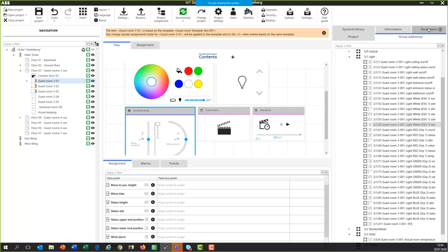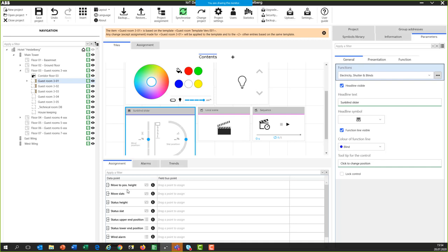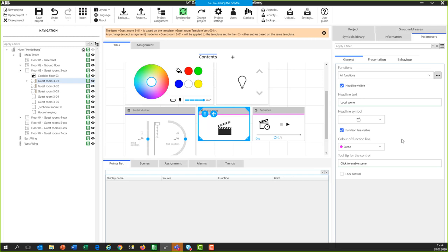For the sunblind shutter control, in the parameters you can adjust icons and text. The assignment objects include move-to-position for height, move-to-slats, status of height, status of upper/end position, and wind alarm. Wind alarm is important: if the end user tries to operate the shutter and there is a wind alarm, they see a red message indicating high priority and that the shutter cannot be operated.